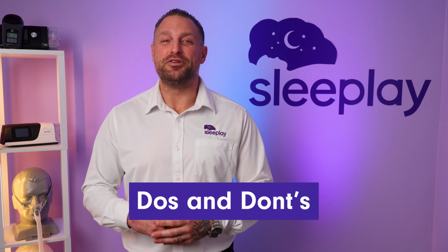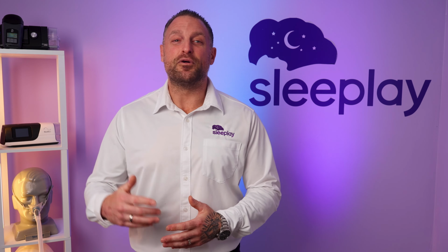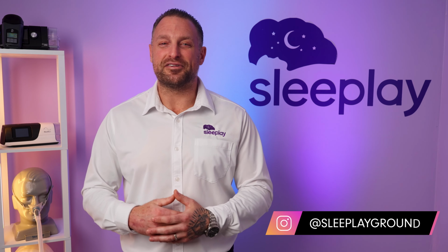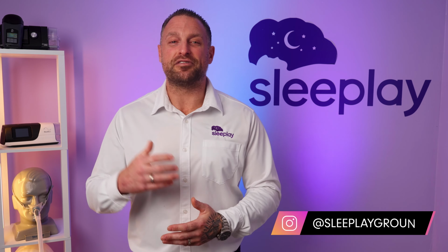The do's and don'ts when using an oxygen concentrator is last, but certainly not least. Avoid using the concentrator in dusty environments. Use voltage stabilizers. Don't let it drop in the water, that's kind of obvious. Don't use harsh detergent or harsh cloths to clean. Use cotton swabs for gentle cleaning.